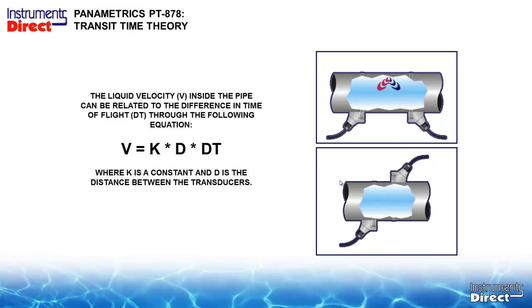The V configuration, or the dual path, is the most common methodology just because it's easier to do. The transducers are on the same side of the pipe. You can see both transducers, and it's usually relegated to pipe size. So for example, the one in the upper right hand corner is traditionally used in applications that are pipe sizes, say 2 inches up to 24 inches. And the one in the lower right hand corner is traditionally used for larger pipe sizes, say 24 inches, or it's also used in applications that have less than the normal straight run of pipe, and smaller pipe sizes, or pipes that are in poor condition. You know, your 50 to 100-year-old crusty old pipe that you need a little extra sound.